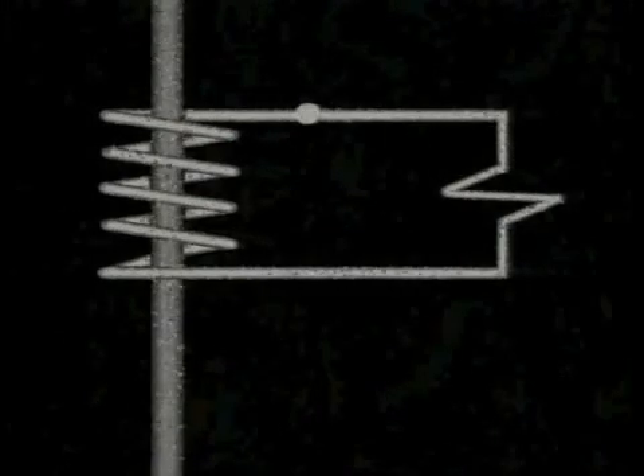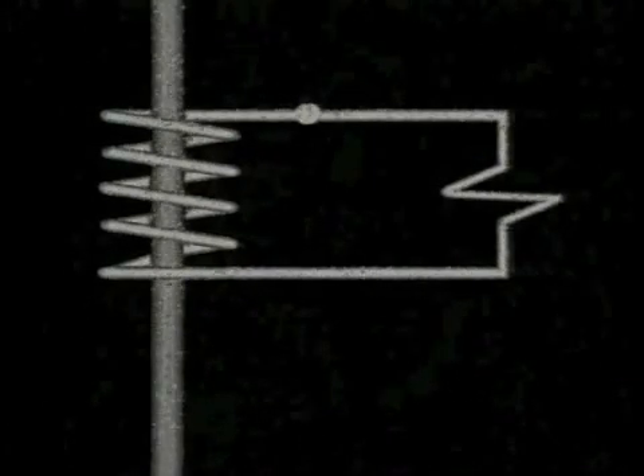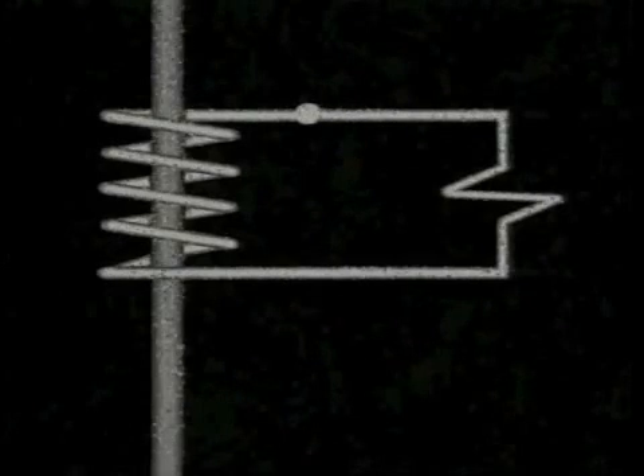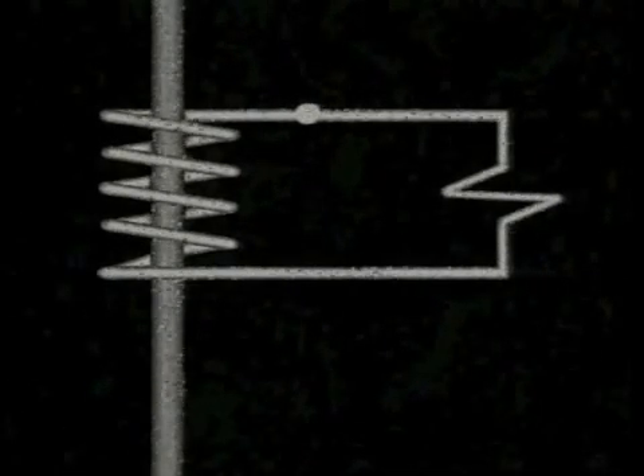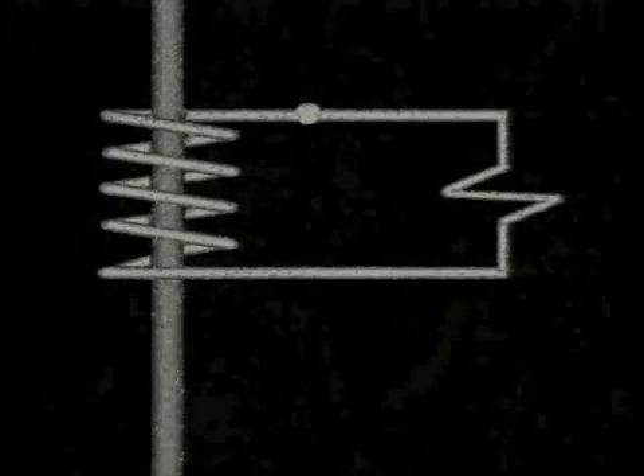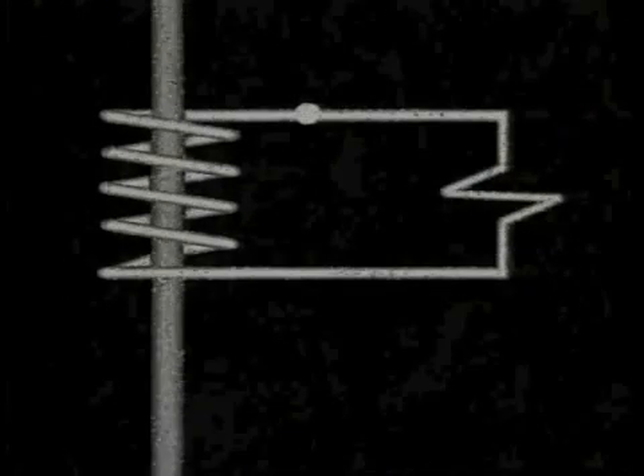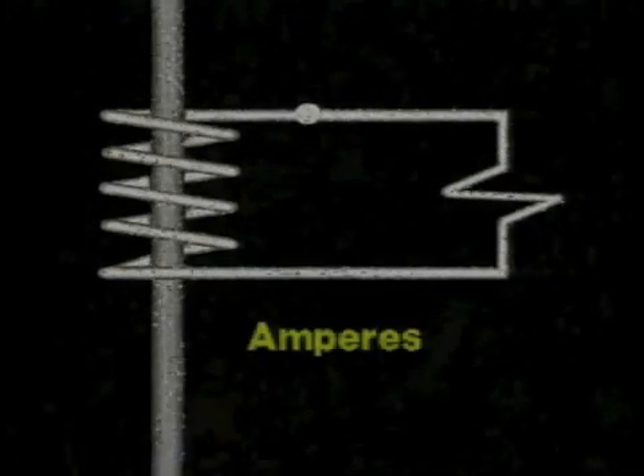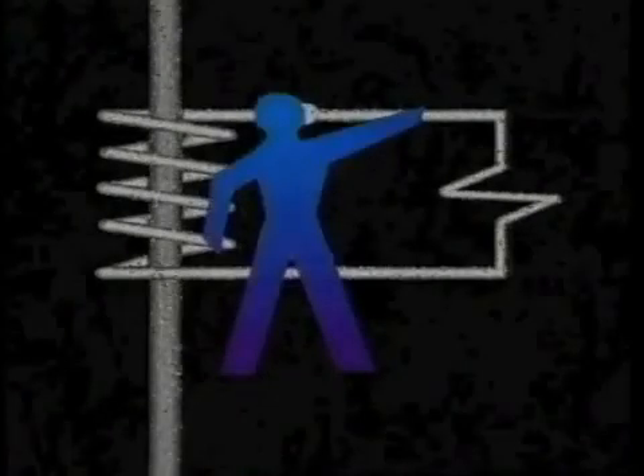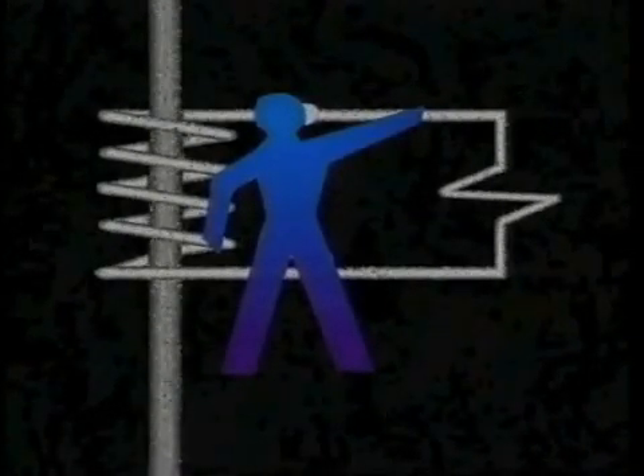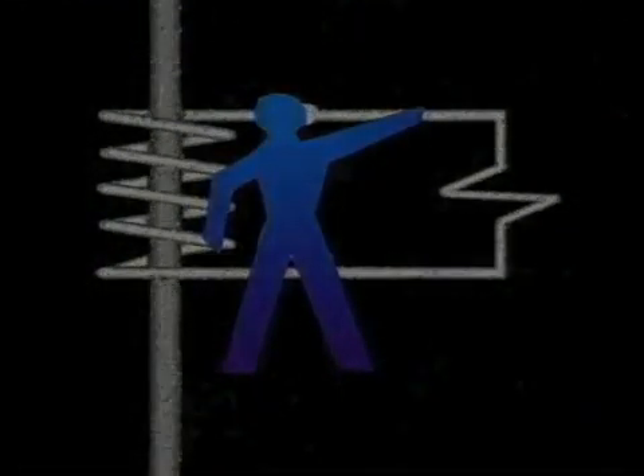Current transformers are used in electrical power systems to step down current. A current transformer's primary purpose is to provide a proportional measurement of the quantity of current flowing in the circuit. The unit of current measurement is in amperes. It would be impractical and very dangerous to measure the full circuit load.